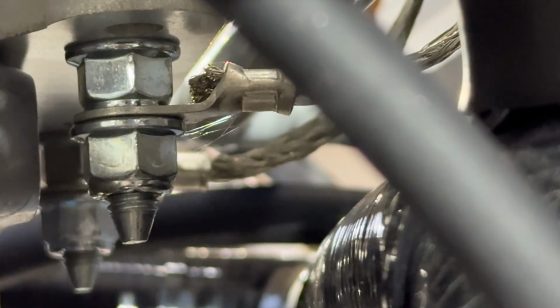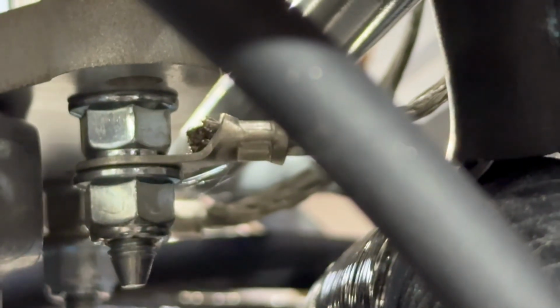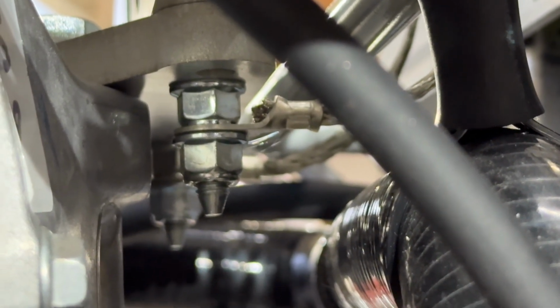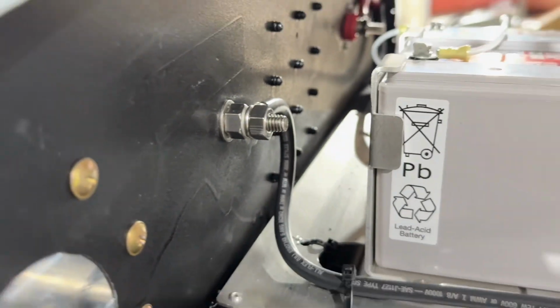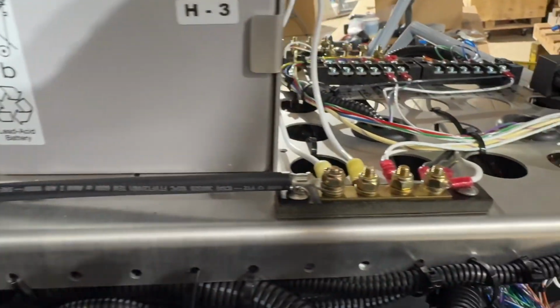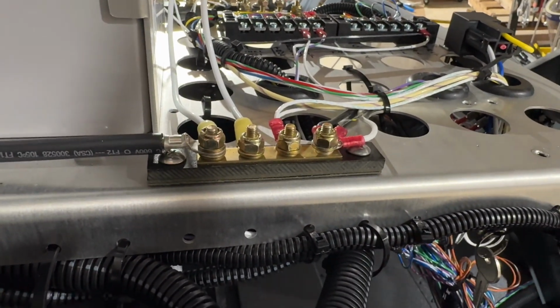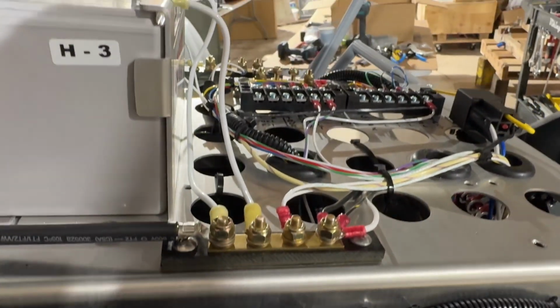We double-nutted that and put a flexible ground strap here, and one back there. They go onto the ground lug, which goes through the firewall, and then from there to the batteries. Actually, they go to the negative ground bus, and then two cables go from there to each individual battery.